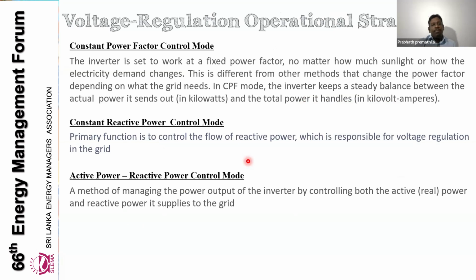The first one is the constant power factor control mode. That's also a voltage regulation operation strategy. For the moment, we operate in the constant power factor control mode, but at unity power factor. We are not requesting any reactive power support. In these situations, whatever the sunlight or however the electricity demand changes, we can set a fixed power factor and ask the inverter to operate. Then the inverter always tries to keep a steady balance between the actual power and the total power it handles. That's also another good option of voltage regulation operation strategy.